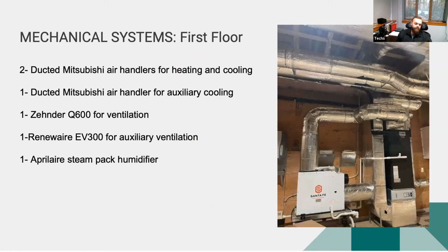On the first floor, we have 2 ducted air handlers for heating and cooling. We have a ducted Mitsubishi system for auxiliary heating and cooling, which is different than most homes. The homeowner likes to have large gatherings, which makes the cooling load higher than the heating. So instead of oversizing the heating system, we installed a separate air handler for when he has parties. We also installed a separate ventilation system for when the CO2 levels in the house get high.